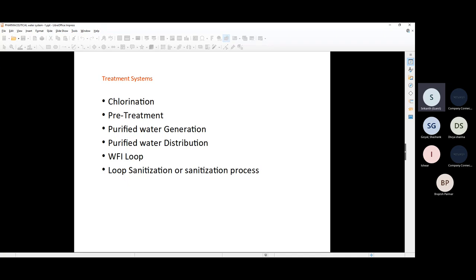The advanced method is that now we are using RO EDI. It will be a double pass RO and the EDI also, based on your conductivity and the EDI capacity. It will be a single or a double pass RO. First, the pre-treatment water will go to the RO, then the treated water from the RO will go to the EDI. EDI means electrodeionization.